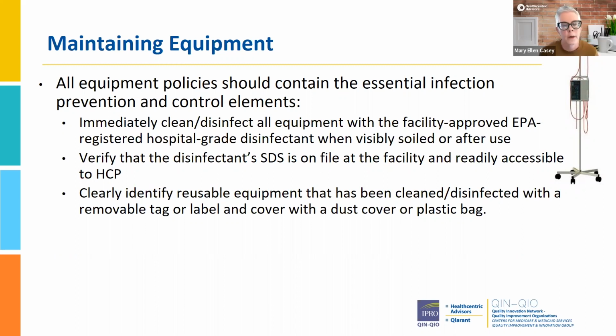So they're really important. Once the equipment is cleaned and disinfected, clearly identify it. This is challenging, especially when you're space compromised. In a perfect world, we'd all have clean rooms and dirty rooms properly labeled, but this has been a challenge. So there needs to be a way to identify what's been cleaned and disinfected and ready for use, whether with a tag or a label. There have been some creative mechanisms to do this — a dust cover, a plastic bag, a room with a sign that says clean equipment only — anything that helps identify the difference between your clean and dirty equipment.